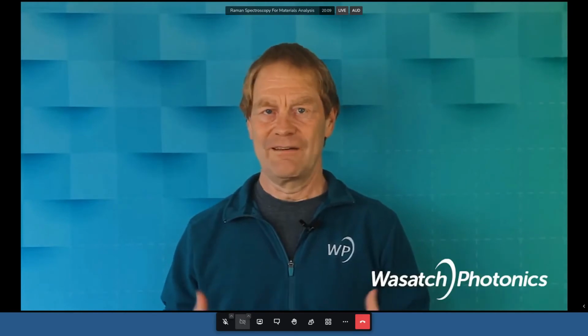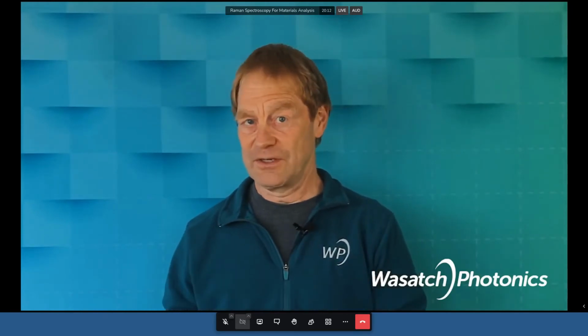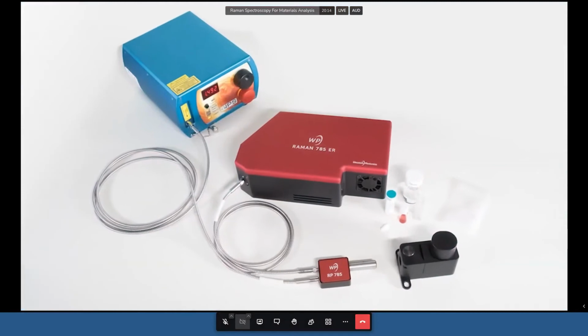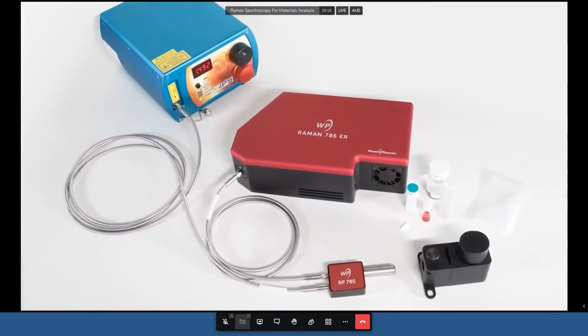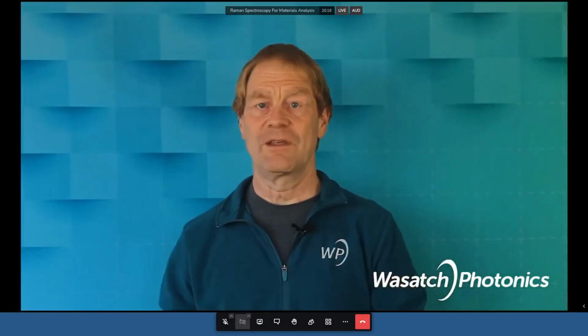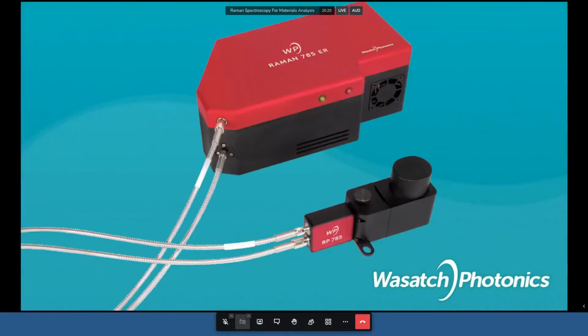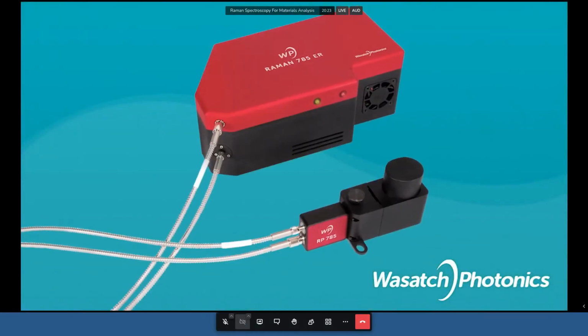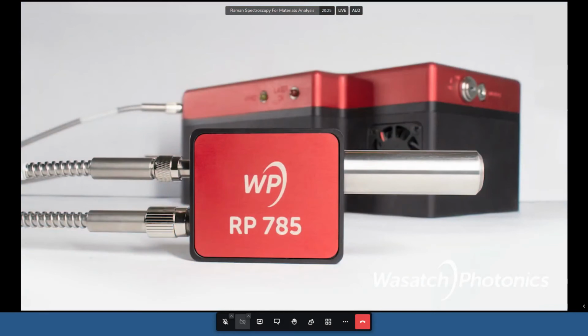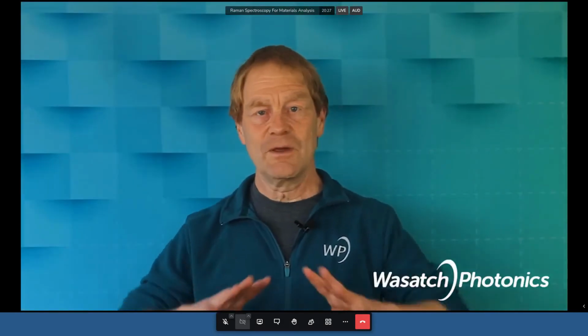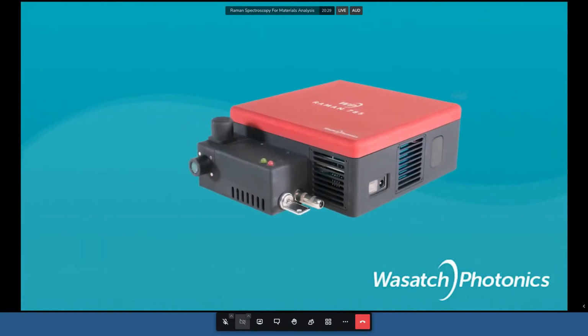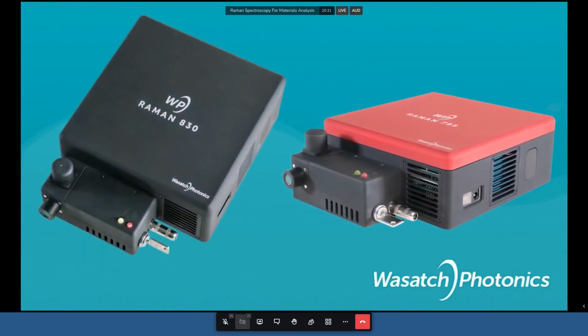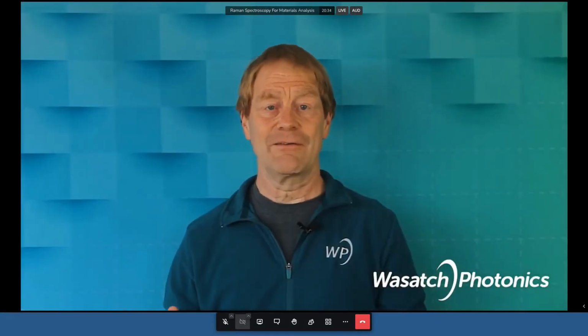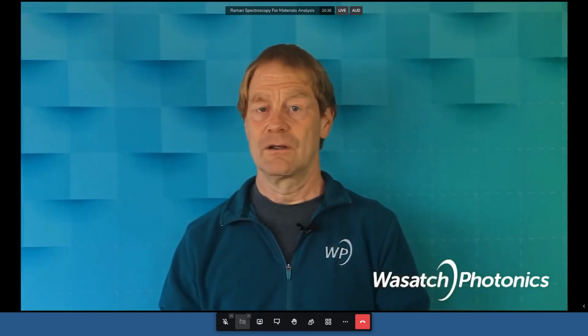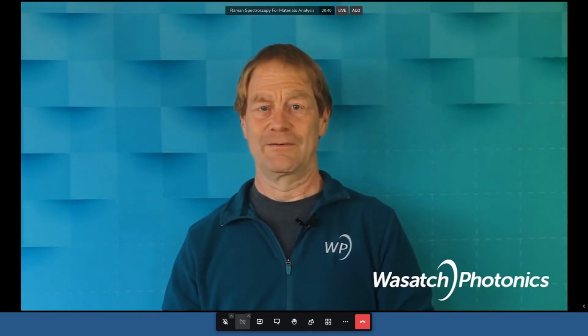WASATCH Raman systems are available in 3 main configurations. The system can be completely modular with separate laser, probe and spectrometer. Our most popular system already has the laser built right into the spectrometer, but the probe is still fiber coupled. And finally, the system can also be completely integrated with the probe and the laser both inside the spectrometer. But whatever system you have, the setup is very similar with only some minor differences. So let's start by connecting the laser.